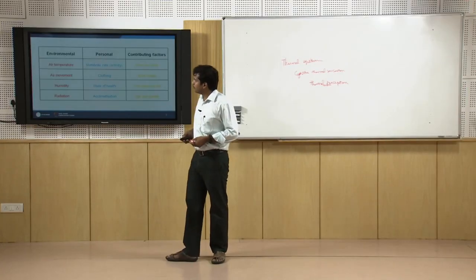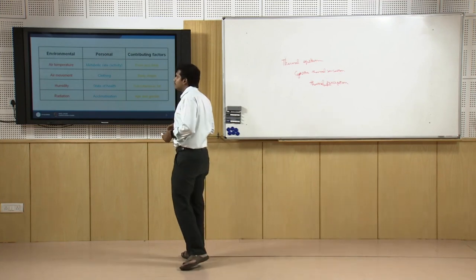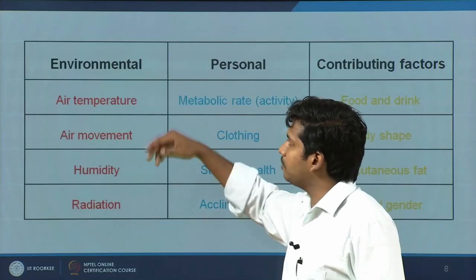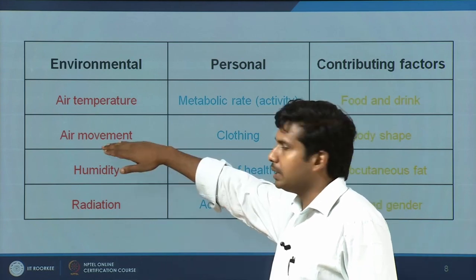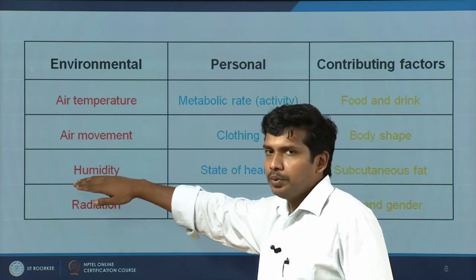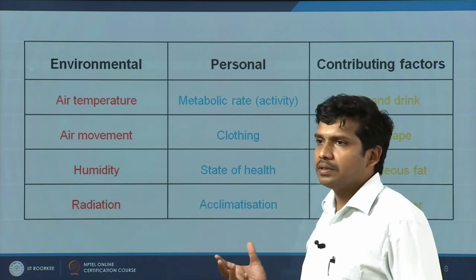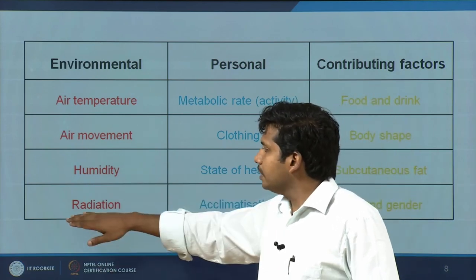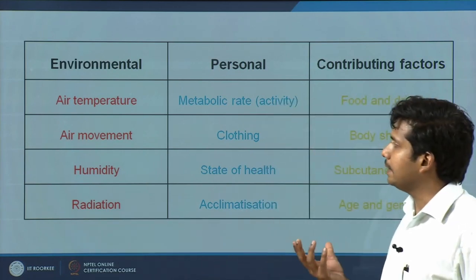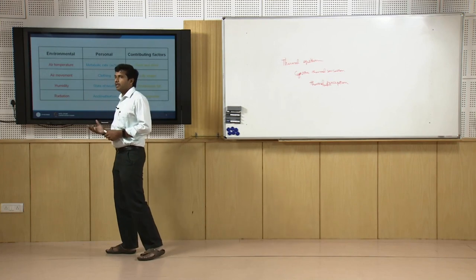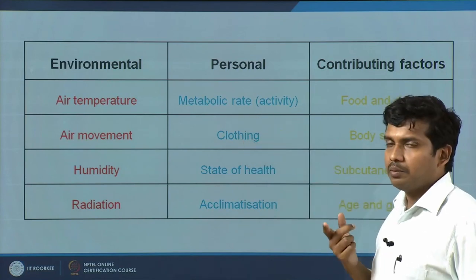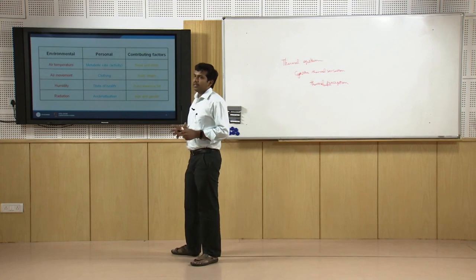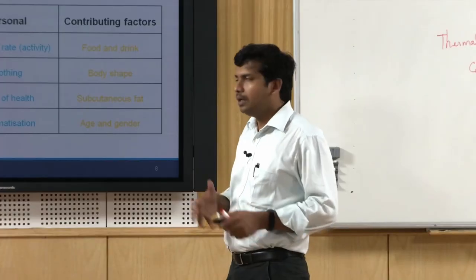What are the factors influencing thermal comfort? There are three different sets of factors. First is the set of environmental parameters: air temperature (referred to as dry bulb temperature), air movement (including air velocity and direction), humidity (relative humidity — the amount of moisture in the air), and radiation controlling radiant exchanges. Then you have personal variables: first is metabolic rate — depending on the activity you perform, your heat generation varies, so the excess heat which needs to be dissipated considerably varies from one activity to another.